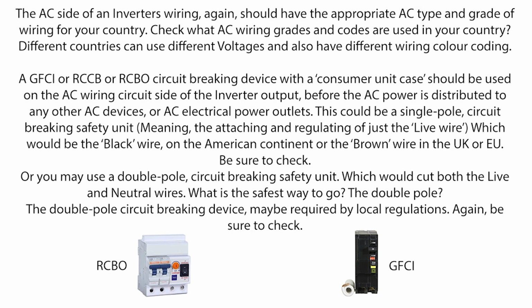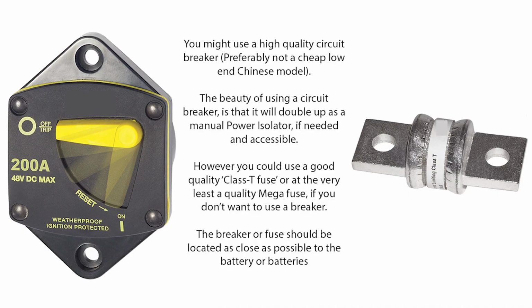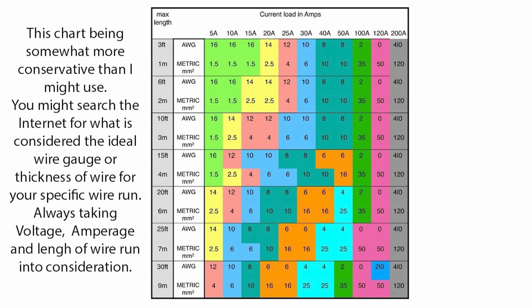However, your wiring, if overloaded, can melt down and can cause a fire. So good quality, appropriate gauge wiring, decent wiring lugs and wiring connections on all the inverter connections and battery connections are of absolute importance. The circuit breaker in my specific case is rated at 200 amps on the heavy gauge battery to inverter cable wire, as my battery is rated at 100 amp. However, it can dish out up to 2C, that being double the rated 100 amp power, as my inverter might have to deal with surges or spikes in AC power demands. That in turn would be converted into surges or spikes on the DC battery side of things.